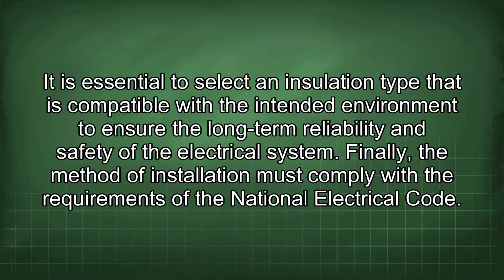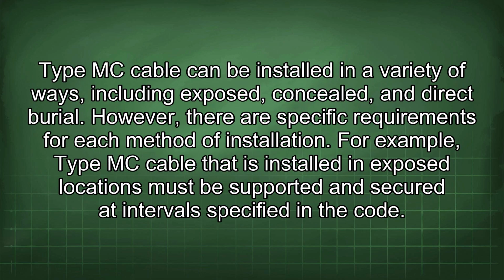Finally, the method of installation must comply with the requirements of the National Electrical Code. Type MC cable can be installed in a variety of ways, including exposed, concealed, and direct burial. However, there are specific requirements for each method of installation. For example, Type MC cable that is installed in exposed locations must be supported and secured at intervals specified in the code.